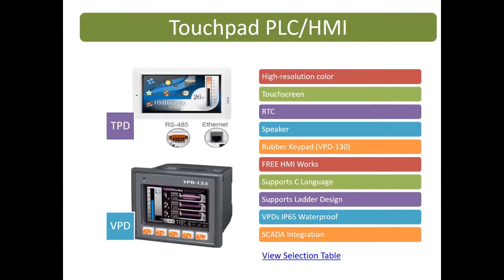Our touchscreen PLCs that have a resistive touchscreen interface, a real-time clock, and a speaker for alerts come with free HMIWorks development software, which allows for making the user interface and creating and running C language or ladder logic programs. They support Modbus RTU and Modbus TCP protocols for integration with other equipment, software, and SCADA systems. Panel mount IP65 waterproof versions are also available.